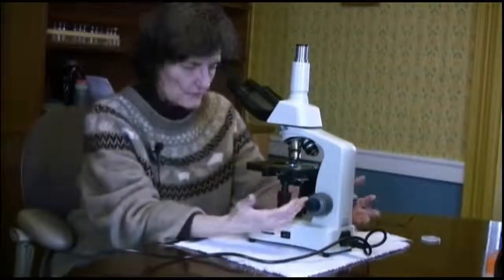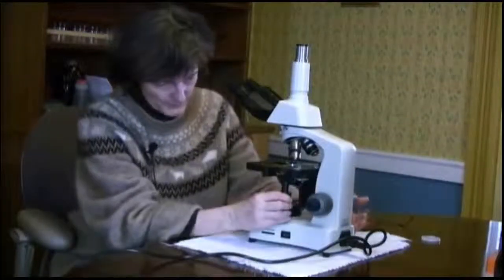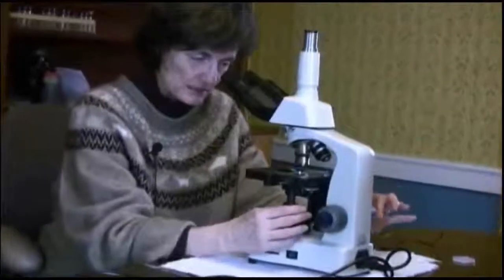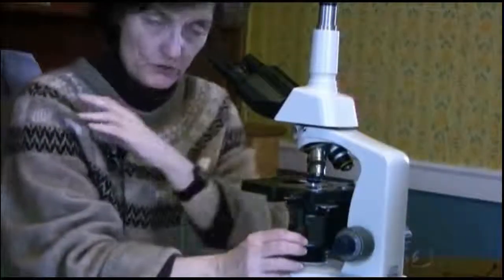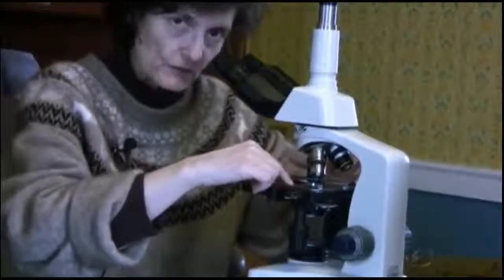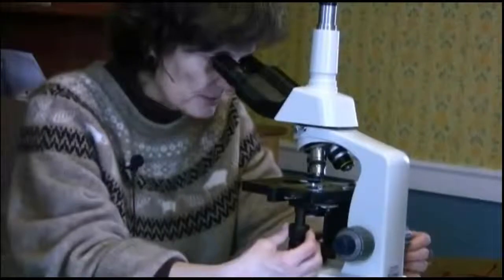When we're looking at the kind of stage, you have to have a stage that you can focus up and down with the coarse and fine focus. But you also want a stage where the microscope slide sits in a holder that moves easily front and back, side to side, so you can very finely, very easily move it very short distances — especially when you're trying to find a ciliate that went zooming across your field of view and you want to follow it. You really need to have the ability to finely control the movement of the slide. If you are trying to move the slide with your fingers, it's just hopeless — you will be very aggravated and won't be able to do a very good job of finding your organisms.